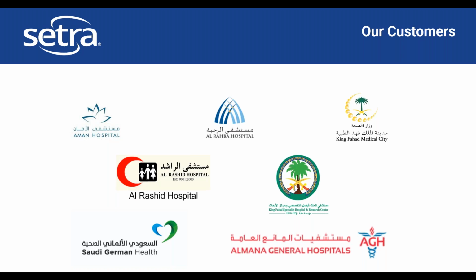So the only product that Setra currently provides that has control is the Flex. So the Flex does provide one output that has a PI loop. So you could do that with the Flex. We do see people control VAVs utilizing the Flex based on pressurization in the room. I guess in theory, you could also possibly control a temp or humidity requirement utilizing that as well. That doesn't answer your question fully, just feel free to type additionally in the space there.